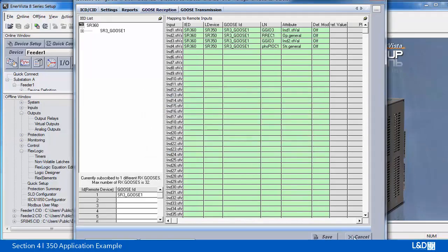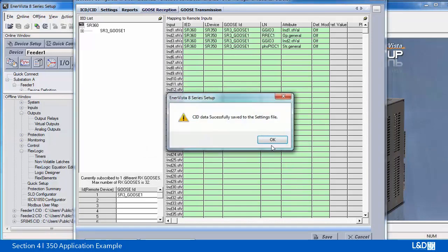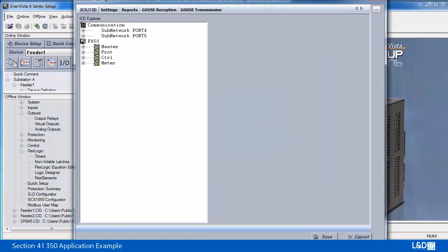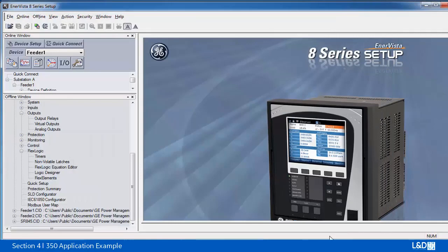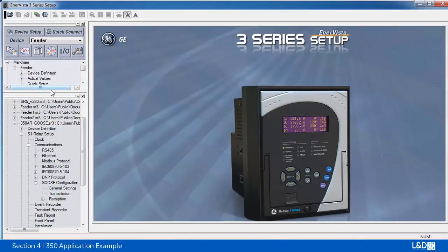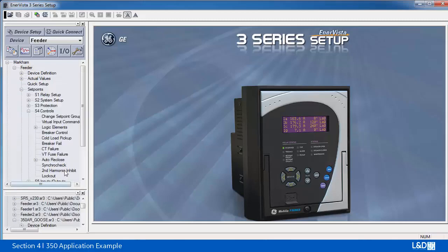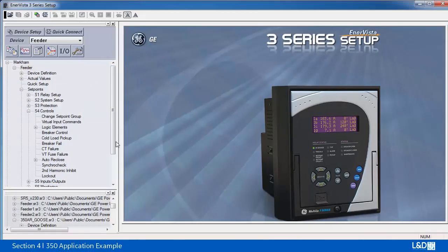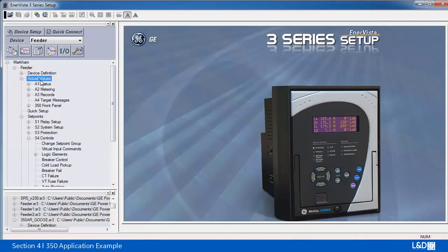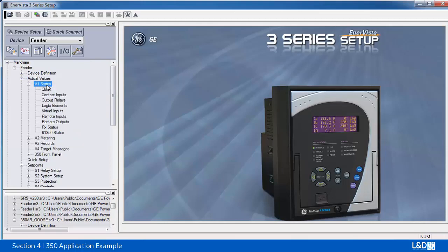Okay, so now we're going to go back into the 3 series and start the auto reclose process. Once the setting file is written to both relays, we need to reboot the relays to make the 61850 effective. Then first thing, we can start the display of the front panel.